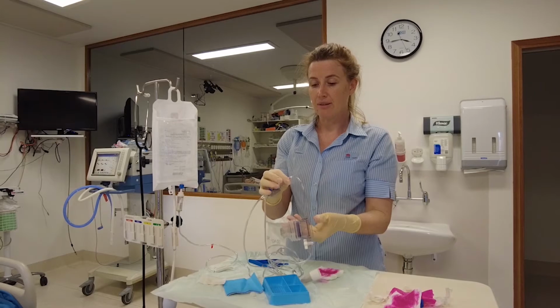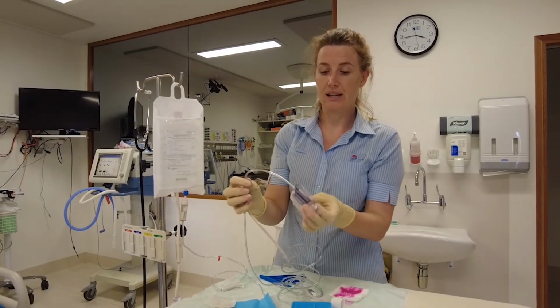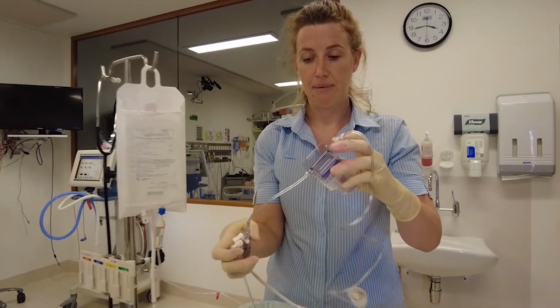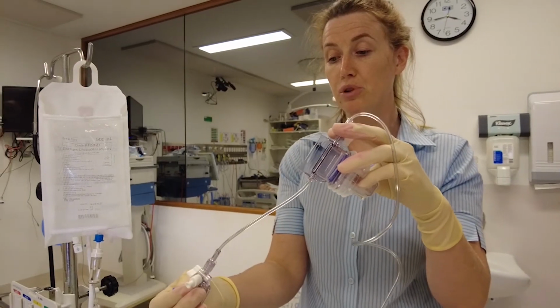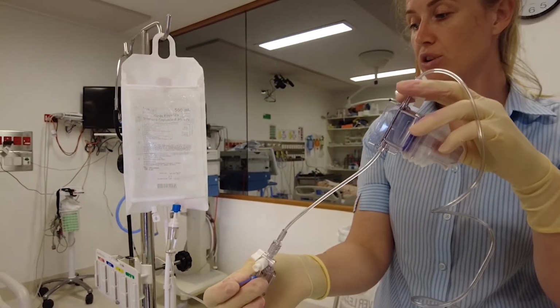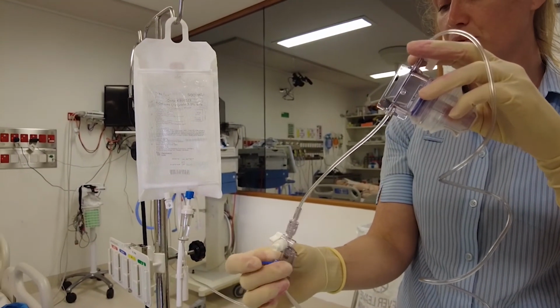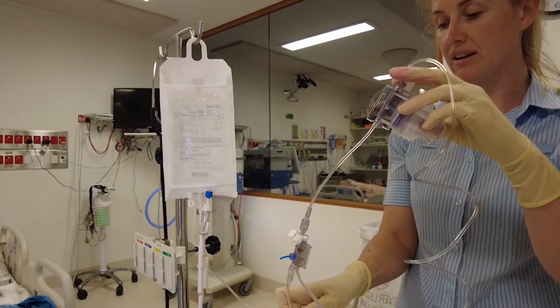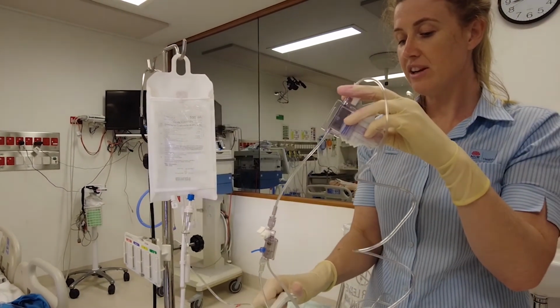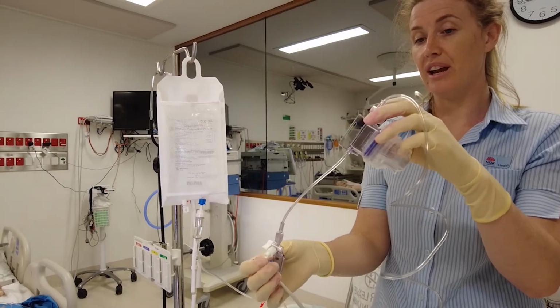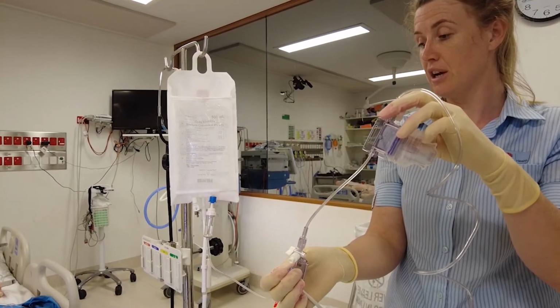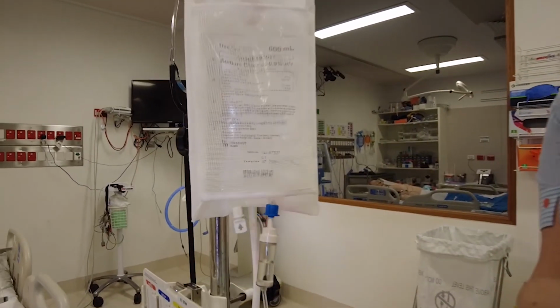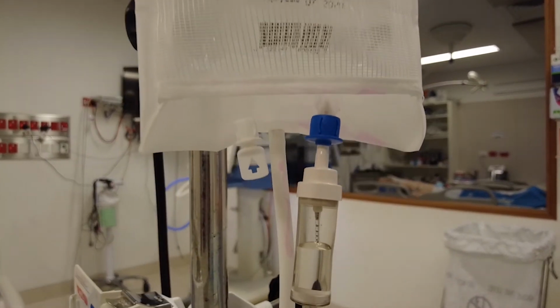What I'm going to do now is start priming, and I'm going to hold this up so you can see it really clearly. Just let me untangle it. So I'm going to be pulling this blue line to do the priming, and you'll notice depending on how hard you pull the blue line, sorry, I haven't unclamped it, let me unclamp it. Depending on how hard you pull the blue line will depend on how fast the saline flows through the system, and I've just pulled that quite fast, so I can already see I've got a couple of air bubbles in my line.